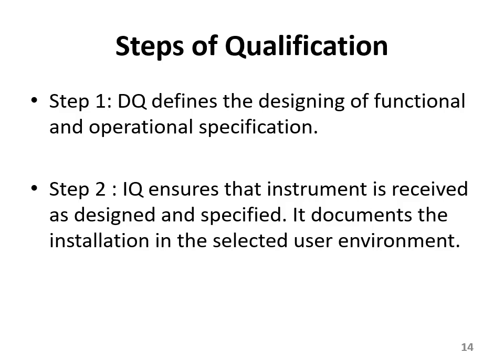Definitely you got your machine, or your product, and now you want to install your machine or your equipment in your environment. Now it is very important: if you are installing an HPLC in Oxford and in Lahore, there is hell of a difference between the temperature of the two areas.